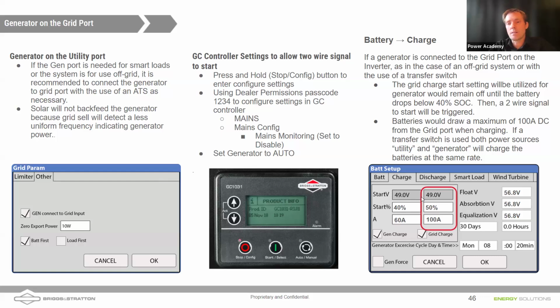Keep in mind that this percentage here is for a device connected to the grid port, and this amperage here is in amps DC. So it'll pull this much amperage DC from that grid port from the generator once it's been started in a grid down situation. So hopefully that's all clear. You can always test your two-wire signal to start by clicking that Gen Force and clicking OK.